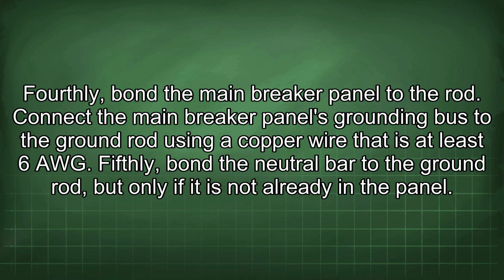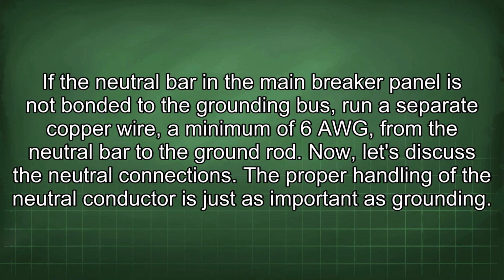Connect the main breaker panel's grounding bus to the ground rod using a copper wire that is at least 6 AWG. Fifthly, bond the neutral bar to the ground rod, but only if it is not already in the panel. If the neutral bar in the main breaker panel is not bonded to the grounding bus, run a separate copper wire, a minimum of 6 AWG, from the neutral bar to the ground rod.